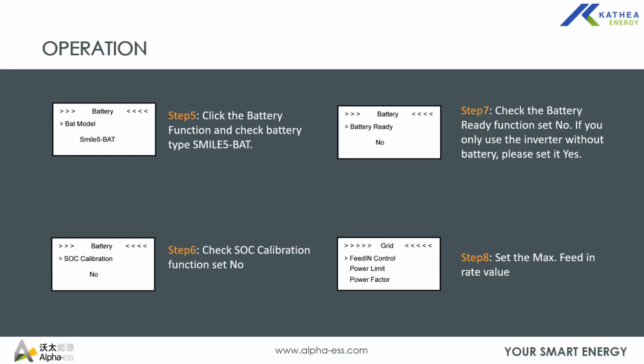And if you scroll, there is also an SOC calibration. You set it to no. Since it's a plug and play situation, the system will automatically calibrate the battery on its BMS. So there is no need for manual calibration of batteries whenever you power on the system. It's default on no, so there's nothing to change there.